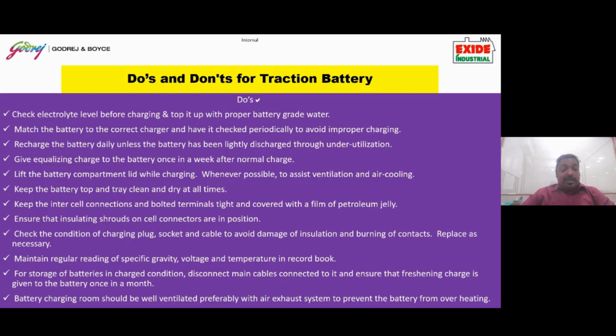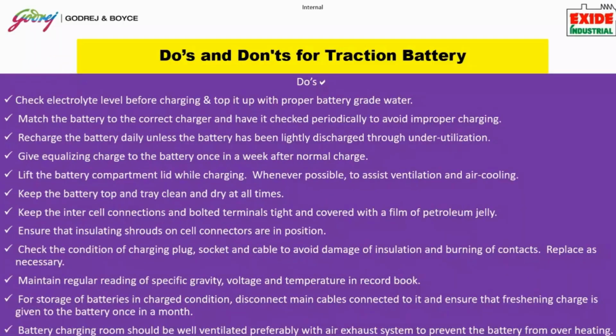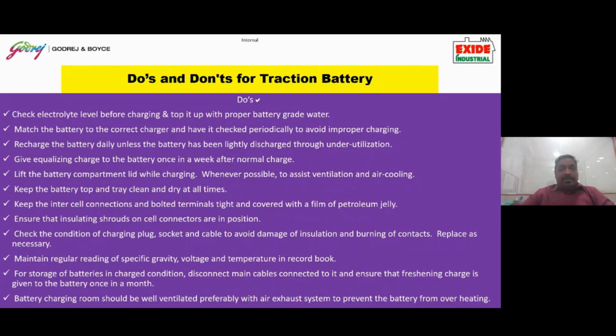And regular readings of specific gravity, voltage and temperature should be recorded during every charge discharge cycle. If the batteries are to be stored in charged condition, then the main cables must be disconnected, and we should give freshening charges to the battery at least once in a month. For any reason, if the forklift is going to be idle for a month or 2 or 3 months, then we should remove the battery from the forklift, disconnect the positive, isolate the battery, charge the battery, and then isolate it and keep it safe in a dry place. And if it is getting stored beyond a month, then we should give a freshening charge one time intermittently in a month.